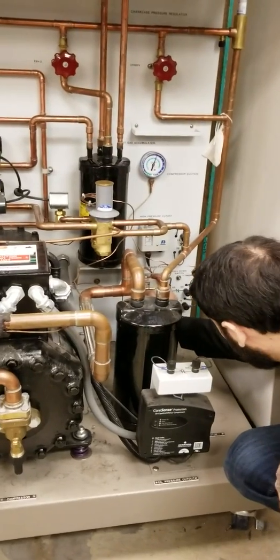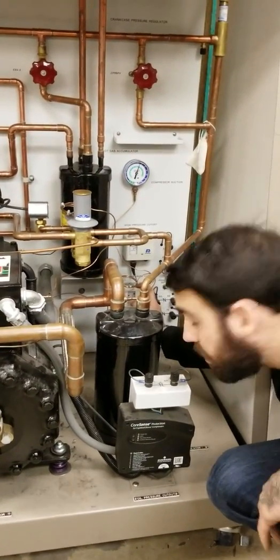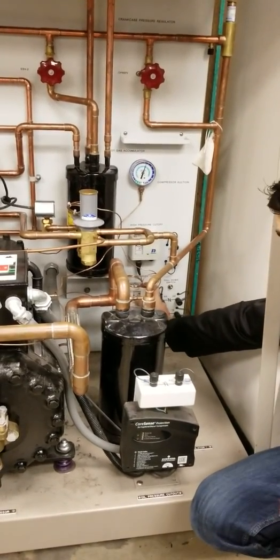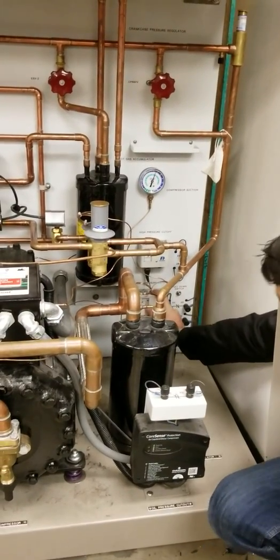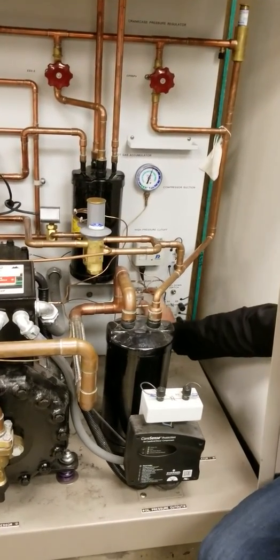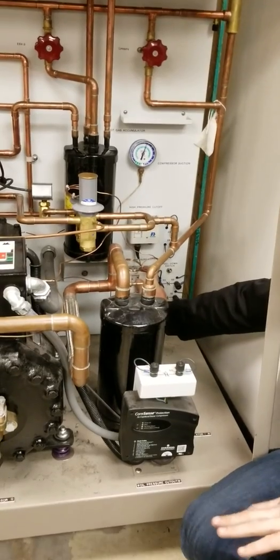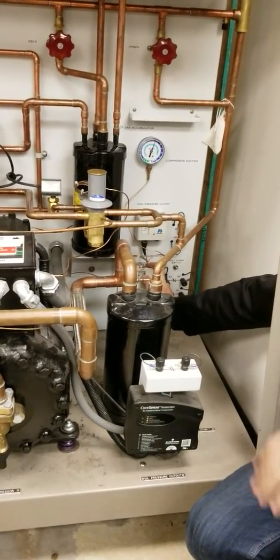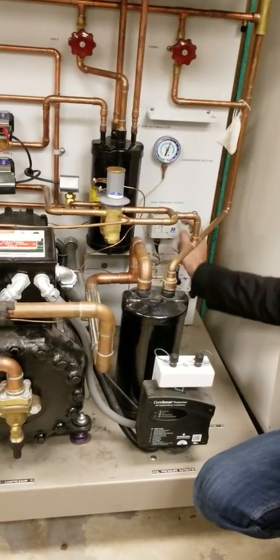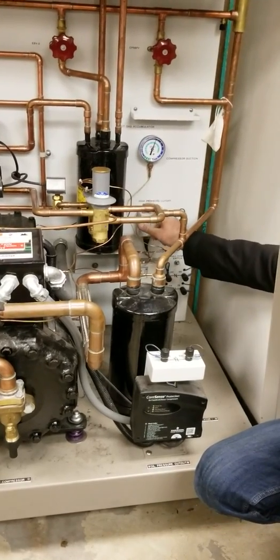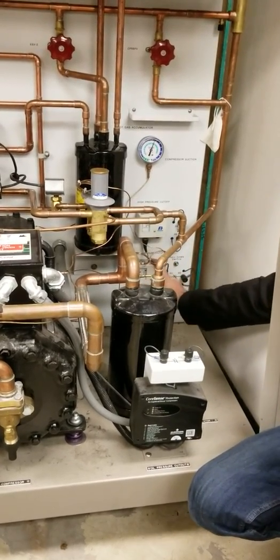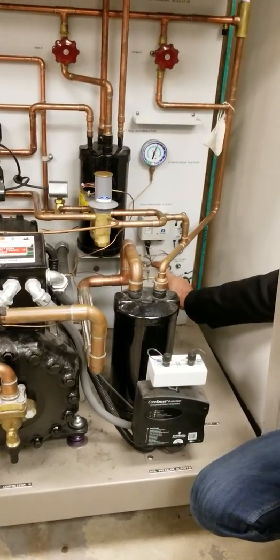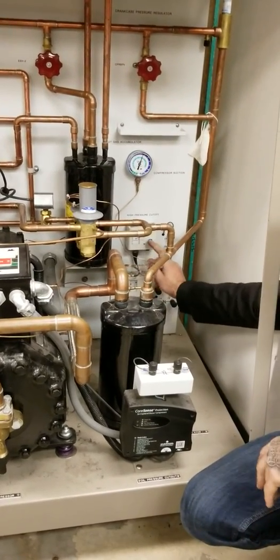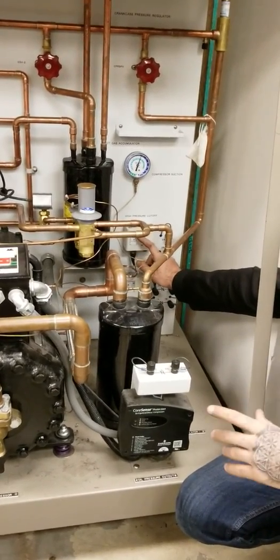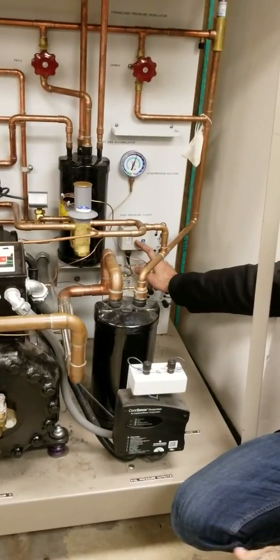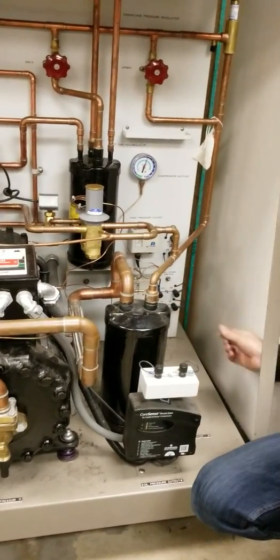If we drop below 10 psi, this thing will kill operation. And then you have an offset of another 10 psi, so it has to rise above 20, and then it'll come back on. And these are adjustable. You have 2 dials on top that could adjust when the cutout is, when it turns off, and then you could adjust the differential so it controls when it allows it to come back on after pressure balances back out.